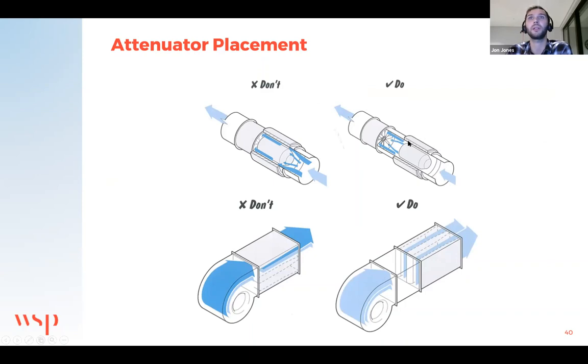At the top here with a circular axial fan and attenuators with a central circular pod. Clearly in this example, you don't want the pod to be fitted directly to the fan. This is going to obstruct airflow, and again, not leave you with the laminar flow, which is what you really want across the attenuator to get the published performance.